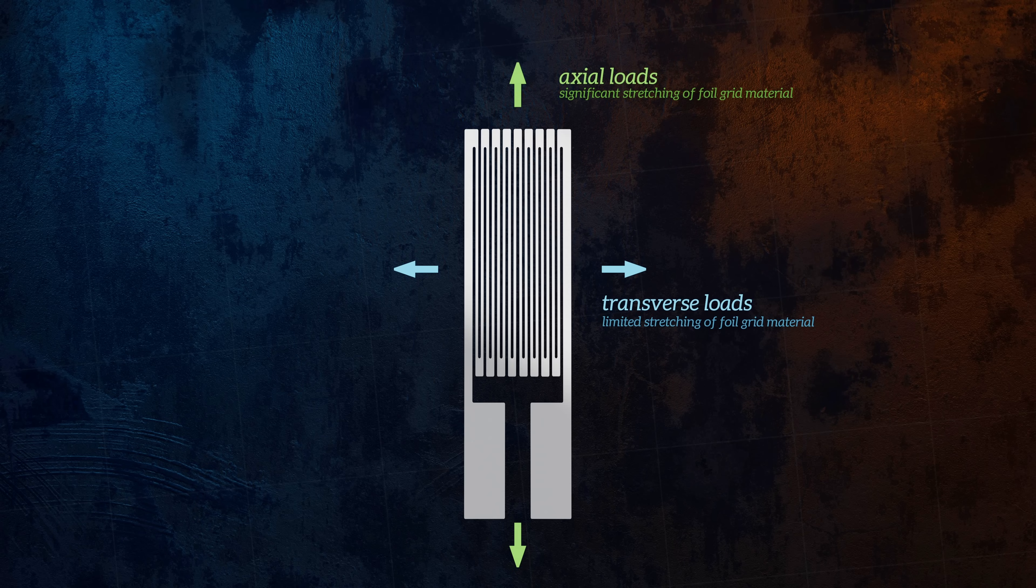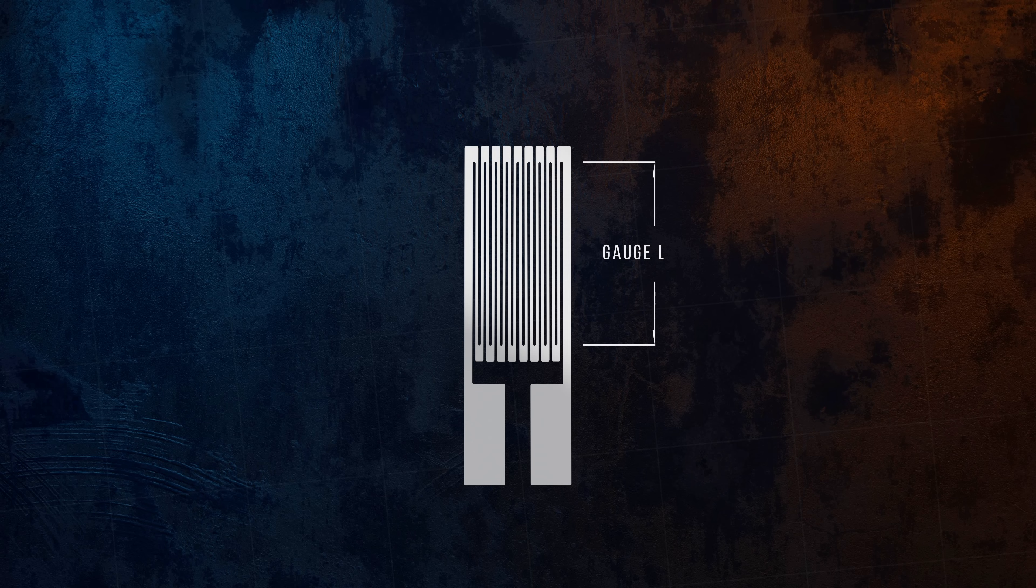The physical length of the grid, called the gauge length, is selected based on the application. The shorter the gauge length is, the more accurately it will approximate the strain at a single point, which is why most general purpose strain gauges are very small.